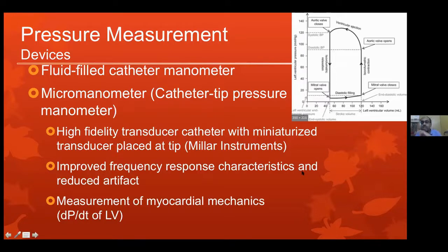Now, the next question that has come up. If the heart rate suddenly changed in the cath lab from 60 to 120, given other things are constant, what change should we do in the setting if required? Actually, we will not be able to make the changes. The pressure transducer has what is called a natural frequency.